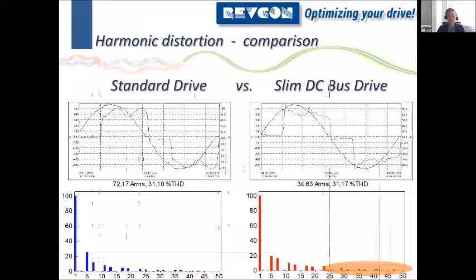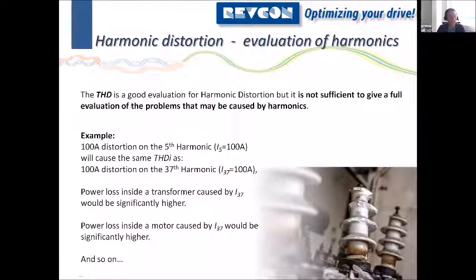To understand why higher order harmonics will cause you more harm, we can make a very long calculation and look at the magnetics of different parts. But we can also just imagine a transformer. A transformer is designed for 50 hertz. And obviously, if you put in 250 hertz, which would be the fifth harmonic, this transformer would still be able to deliver quite a big part of this to the next medium voltage level. So a small problem, because a small part will be transmitted into heat, but not a huge problem.